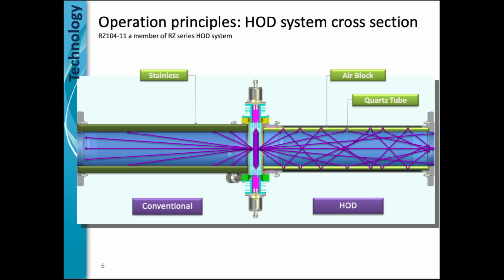They elected to reduce the energy in the HOD chamber to optimize energy and performance. As they dropped the energy from 100 millijoules, 80 millijoules, 60 millijoules, they achieved 99% control at 40 millijoules and 90% control at 20 millijoules, ultimately agreeing on 40 millijoules for design. But did the organism change and inactivate by the energy of 40 millijoules? No, the HOD UV concentrated in a section of chamber to mimic 100 millijoules.